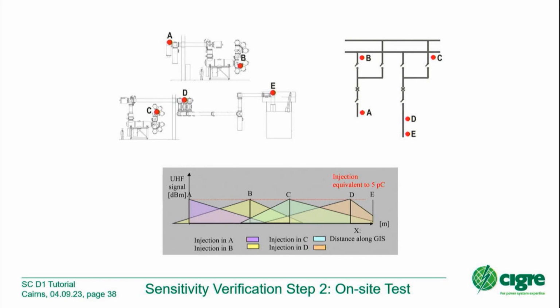A void in an insulating rod was maybe the root cause of the defect. From my basic understanding, a typical void should give a very broadband frequency response. The ultra high frequency method was chosen in former times based on the low number of noise signals in that frequency band, and so the UHF method has a big advantage compared with IEC 60270. Whether it is better at VHF, very high frequency, which is maybe 50 to 200 megahertz, or UHF, in that case, from my personal view, this should not give any difference.